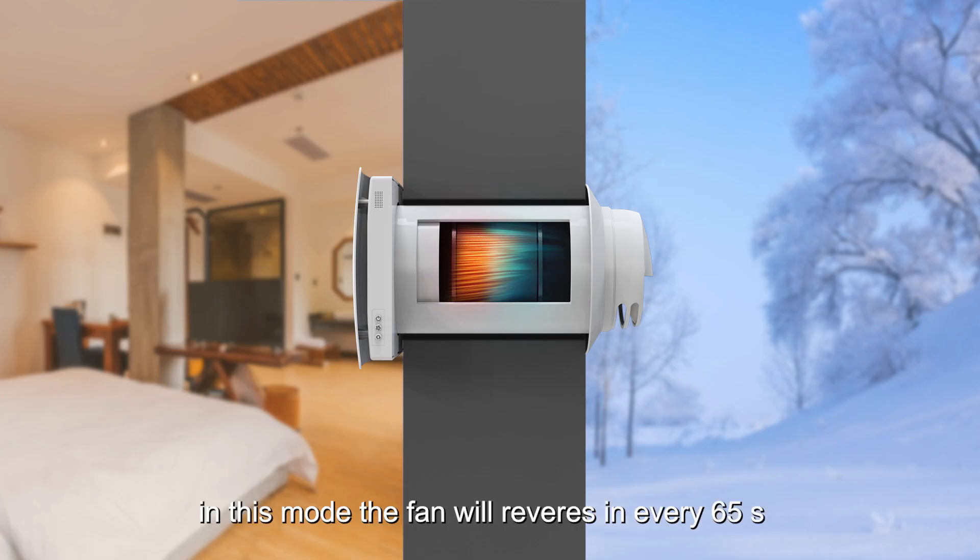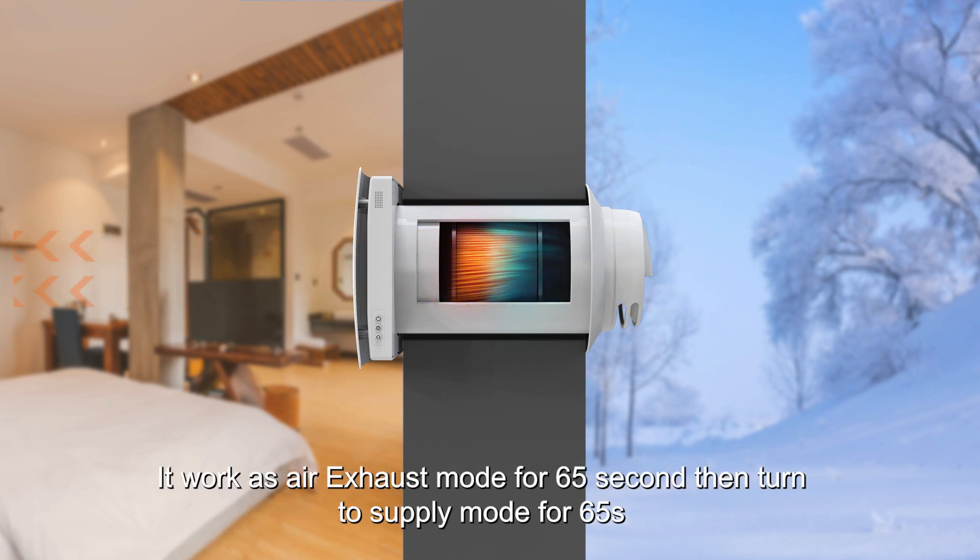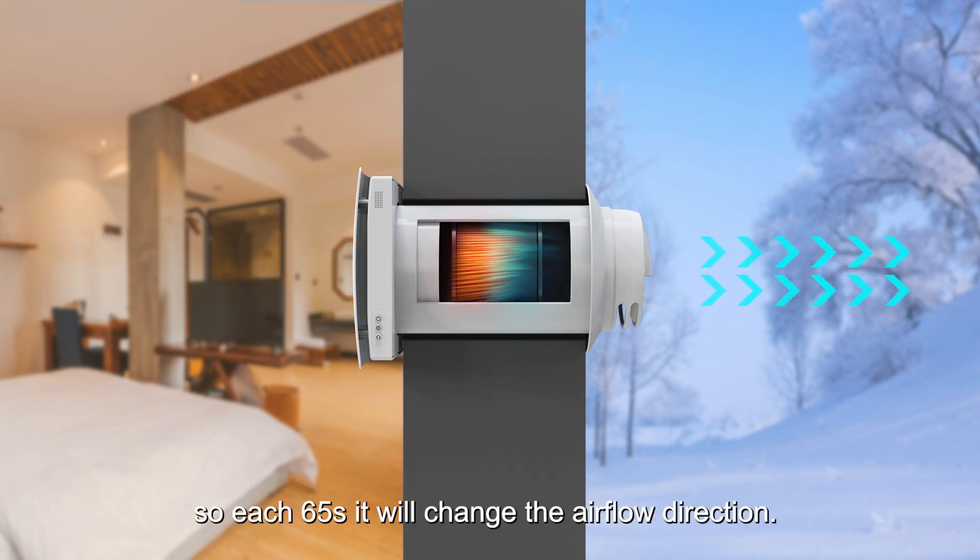In this mode, the fan will reverse every 65 seconds. It works as air exhaust mode for 65 seconds, then turns to supply mode for 65 seconds. So each 65 seconds, it will change the airflow direction.